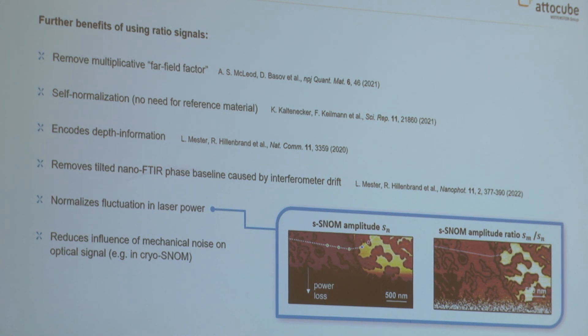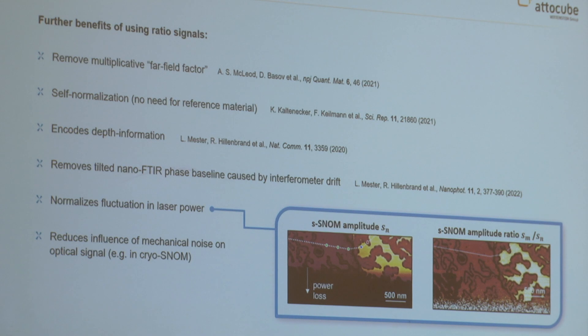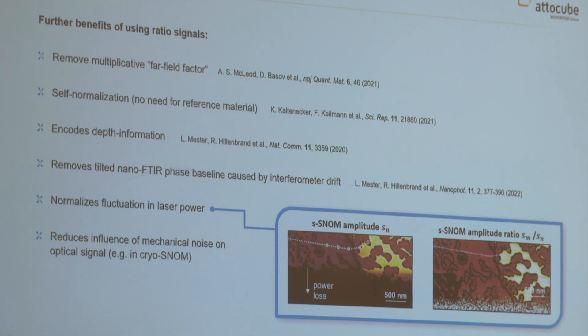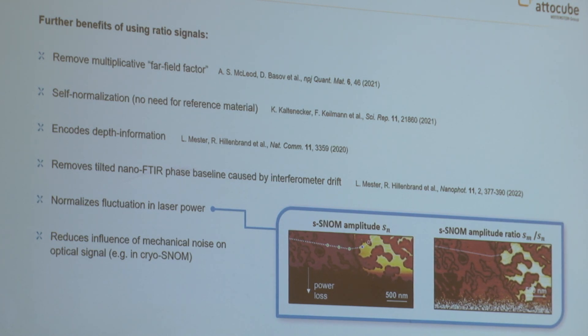If it happens that your laser turns off during the measurement and is losing power slowly — this happened here, for example, where the amplitude just drops down to zero — this can sometimes happen, especially in long experiments. Normally I would measure again, but this is not always possible. You can try using this ratio to recover some of this information. And if you look at the substrate or the contrast here, it's not affected at all, because essentially this is like an illumination effect: you have more or less power. And one last application, which was used in the first version of the cryo-SNOM: mechanical vibrations in the system may knock the tip a bit further away from the sample, which also leads to a smaller near-field signal. Such a normalization to different harmonics helped reduce this a little bit.